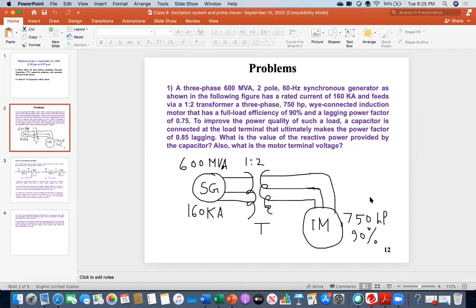Now find the Q new. It's 0.386 megawatt, right? Yeah, that's right. Now you are on the right path. So finally you should be getting the capacitor reactive power at approximately 163 kilowatt, or 0.163 megawatt. I got 162.99 something, so I approximated to 163 kilowatt.